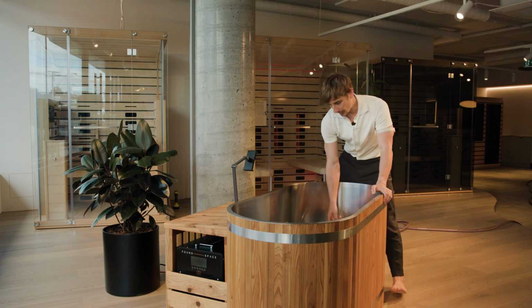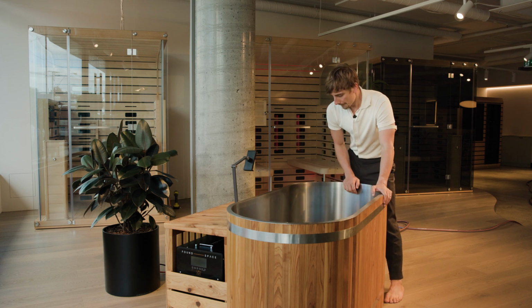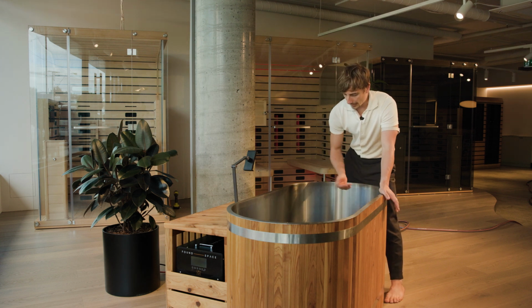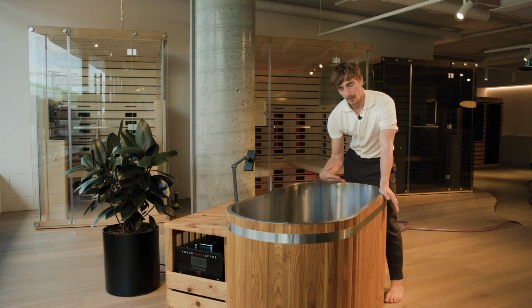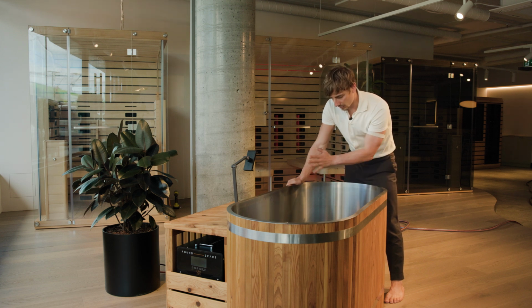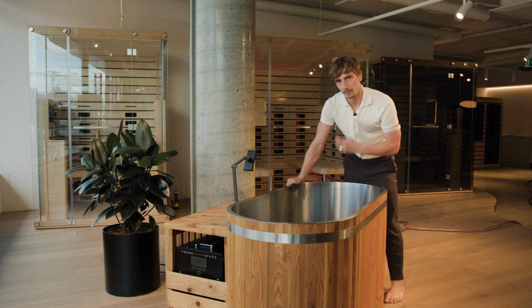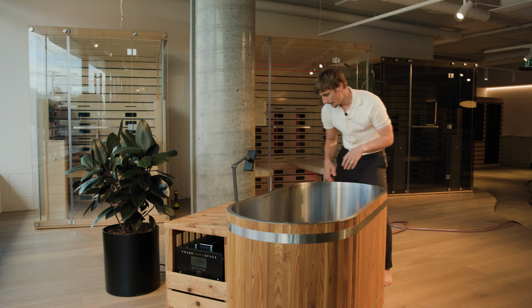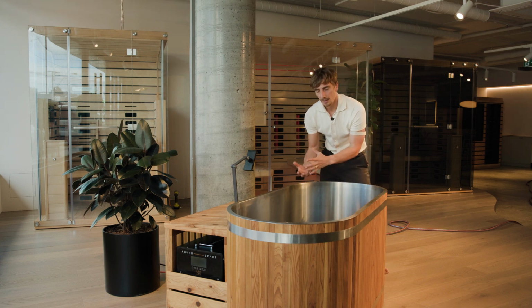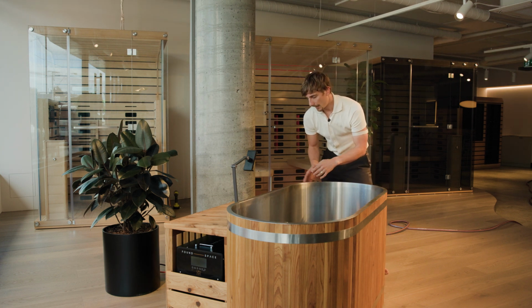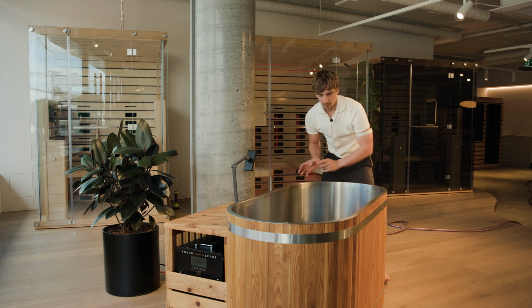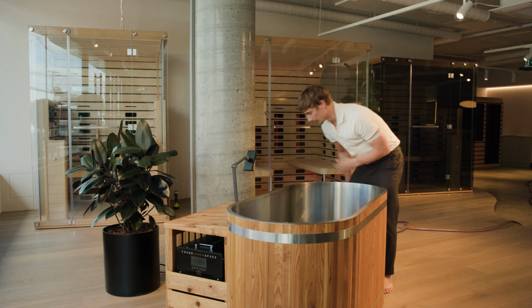Make sure the plug in the bottom is closed. We want to fill the Yirri up to a bit above the inlet into the chiller before we turn the chiller on. Also make sure you've changed the filter, which we'll talk about later, and that it's all packaged up and ready to go. Then we can start to fill the Yirri.